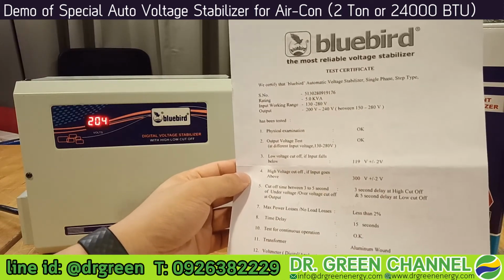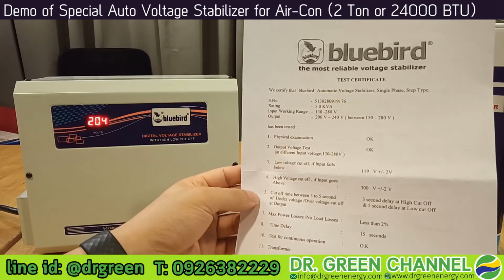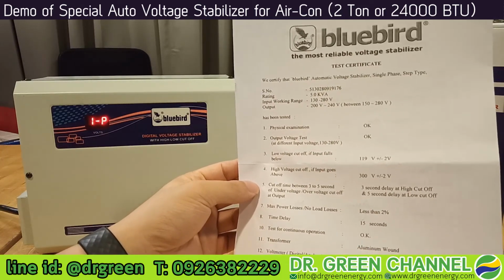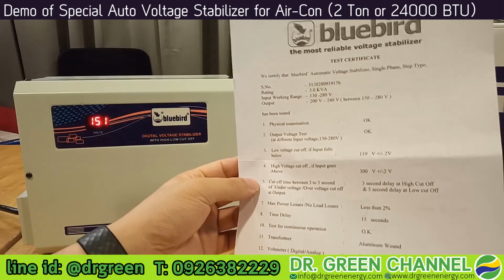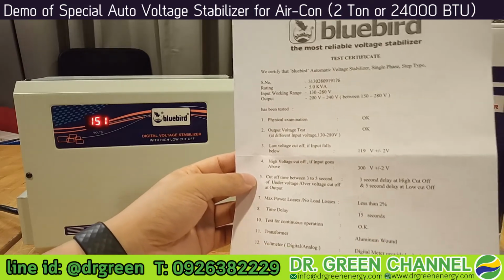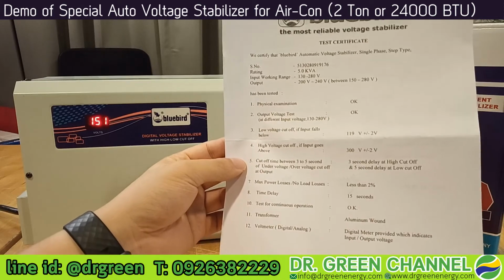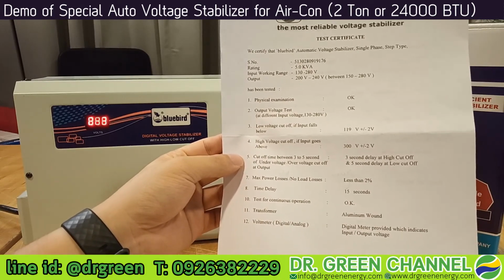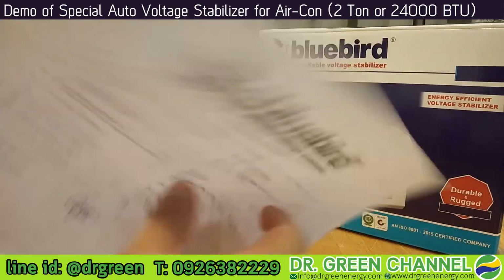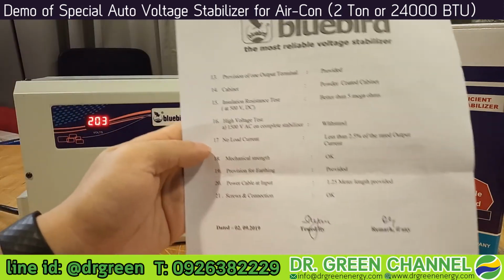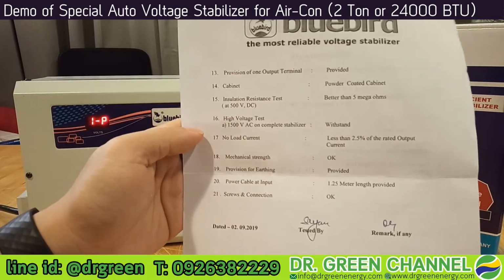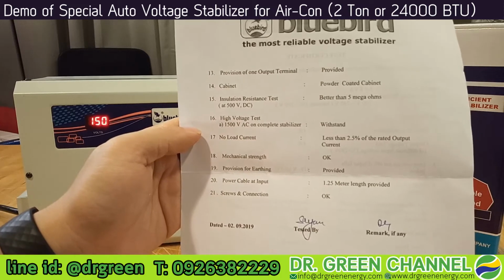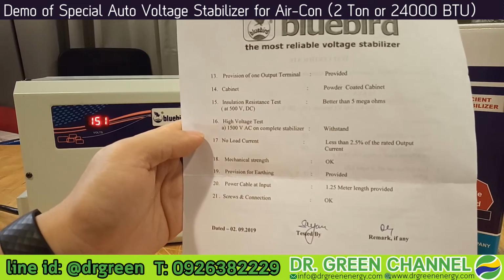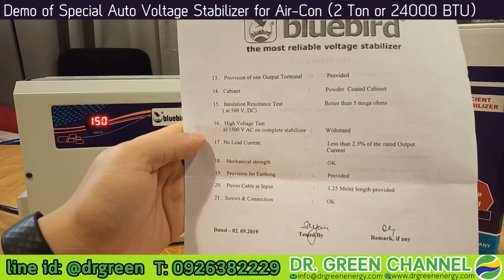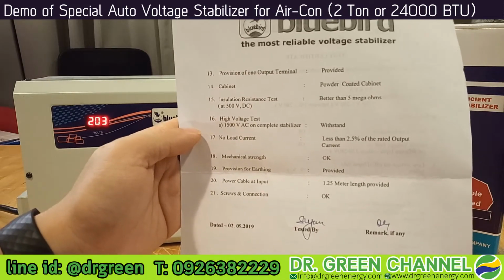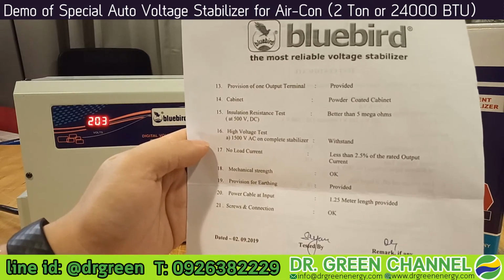So bear with me for this. It has the cutoff for high voltage and low voltage to save your air conditioners. The transformer base has a digital display, and on the back, for safety, it's written better than 5 mega ohms for the insulation resistance test. So this is a very good quality stabilizer.